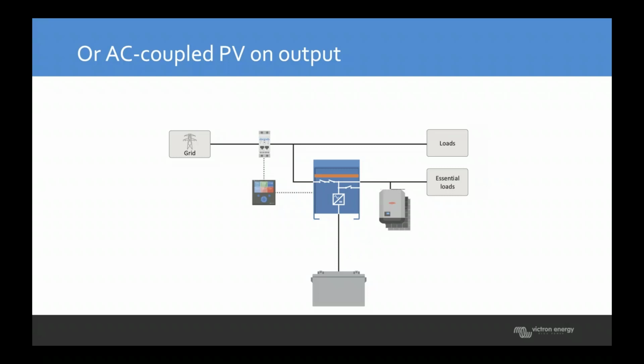But in this system, if the grid drops out and that AC sine wave is disconnected, then what happens is that the Victron Multi-Plus will create the sine wave instead. It'll take over, it'll form that grid wave, that sine wave, on the essential load circuit, and the Fronius will synchronize to that instead. So you can still charge your system during a power outage when the system's like this. Now, there are limitations on a system like this, which we'll talk about in a little bit more detail.